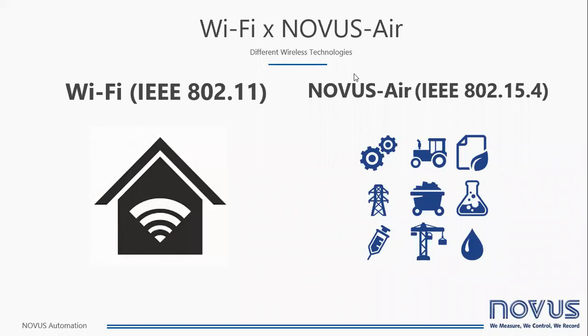So if we're talking about the robustness of the physical layer, we have the same as wireless HART, so that's good news for us. But the difference is on the protocol. Wireless HART talks HART, okay, and we talk Modbus, so we exchange packages on Modbus. The advantage of that is Modbus devices are offered and available in the market with more competitive prices, in my opinion, than HART, and they are much more flexible, okay?